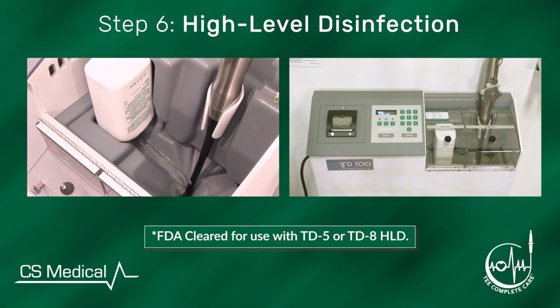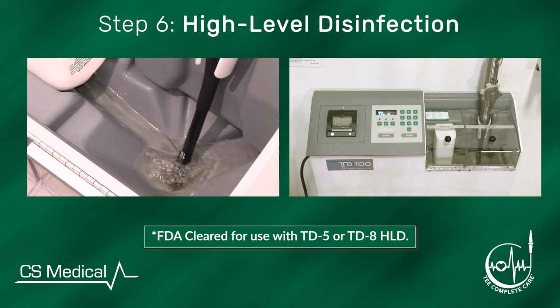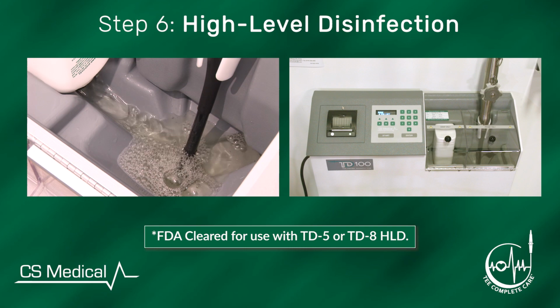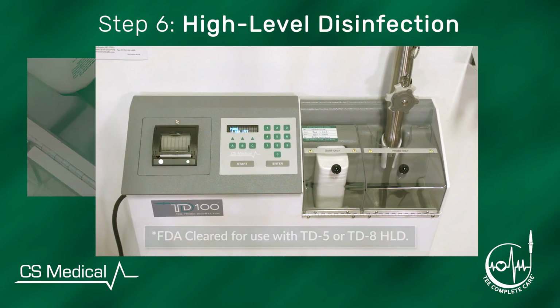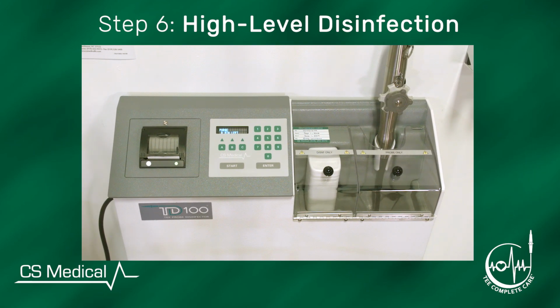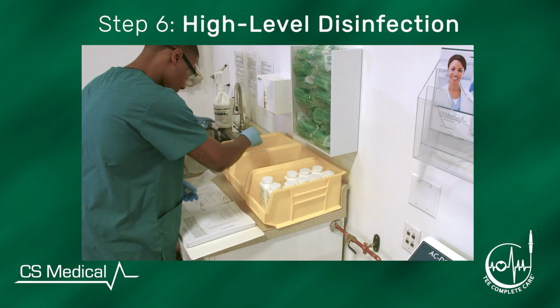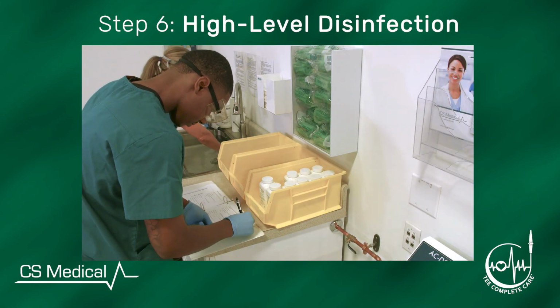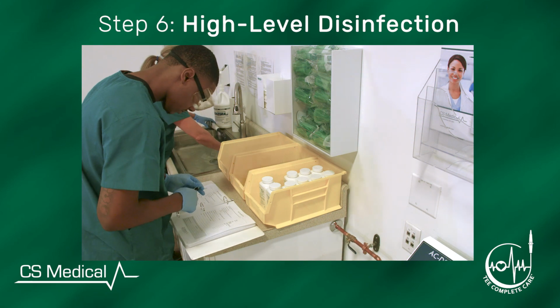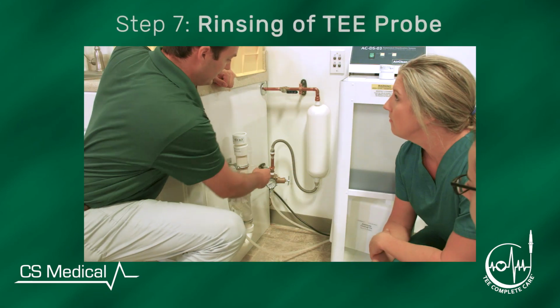The TD100 is FDA cleared for use with either TD5 or TD8 high-level disinfectant. During the disinfection process, the TD100 constantly monitors disinfectant contact time and temperature. And at the conclusion of a successful cycle, the verification report is generated and can be logged in the HLD tracker for later reference.